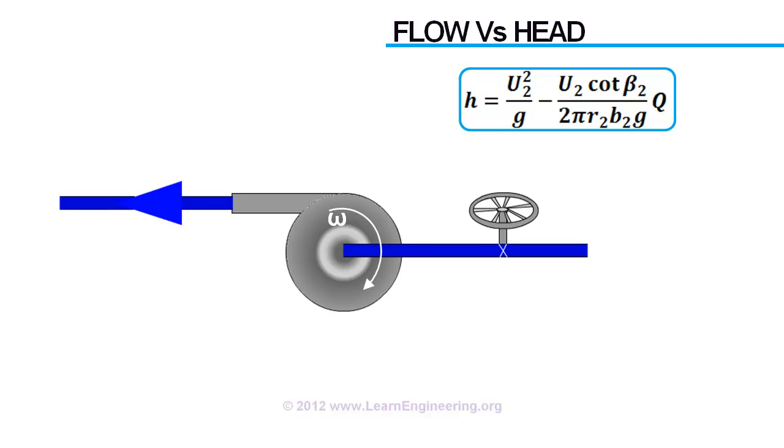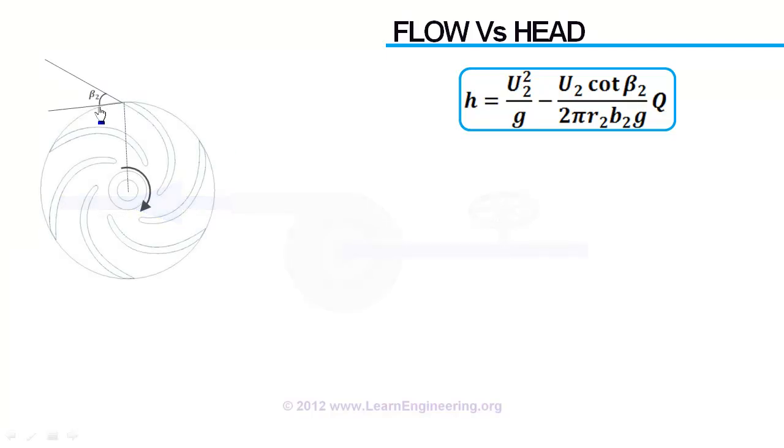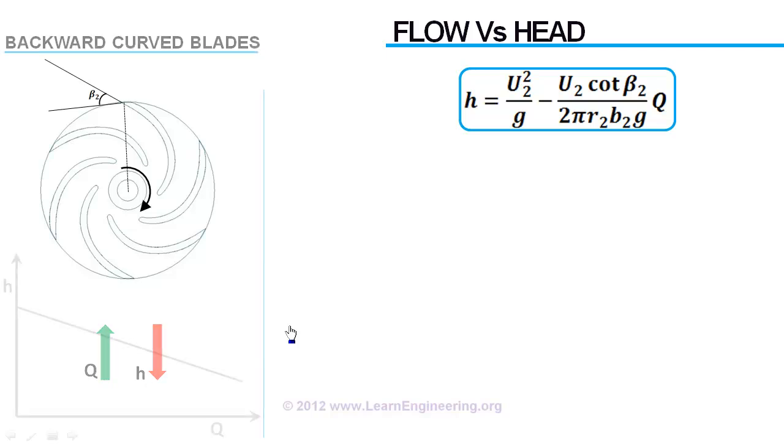First case, if beta is less than 90 degrees. Since this term is positive in this case, pressure head decreases with increase in flow. These kinds of impellers are called backward curved.